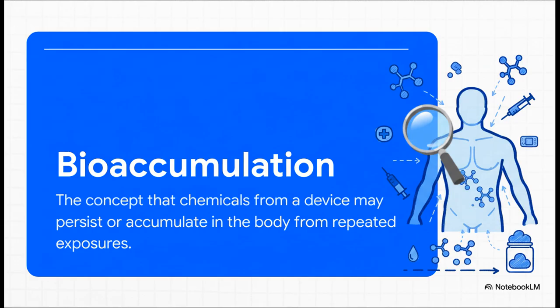So you're probably asking, why this crazy change? Well, it's not arbitrary. It's all based on the scientific principle of bioaccumulation. The idea is that even from really short repeated exposures, chemicals from a device can build up or accumulate in the body over time. The standard is now forcing everyone to account for this cumulative effect, not just the simple sum of contact minutes.